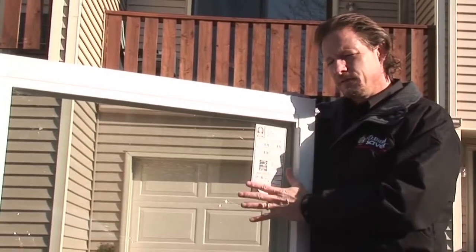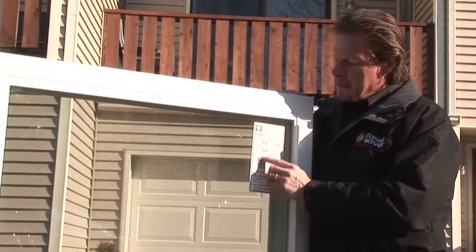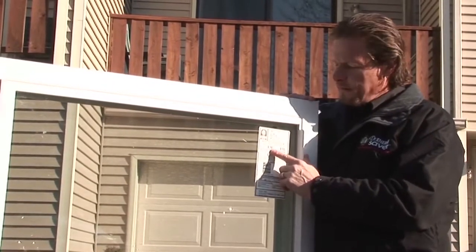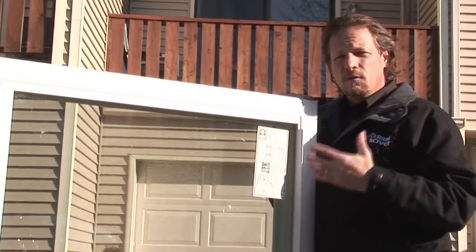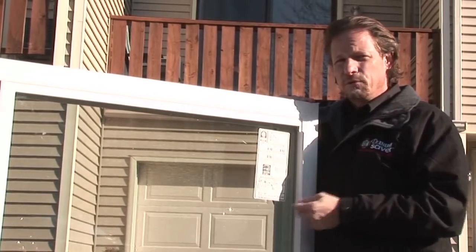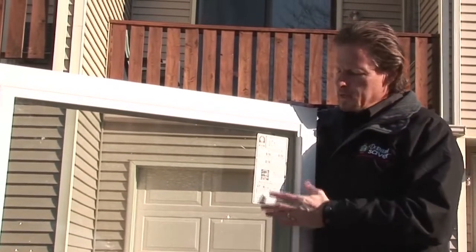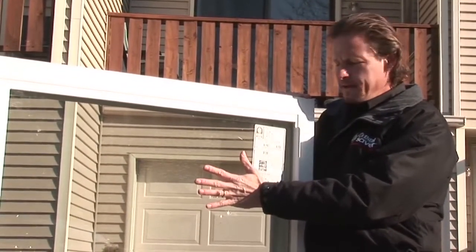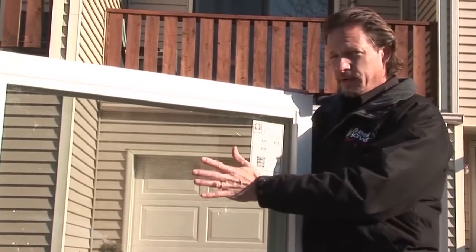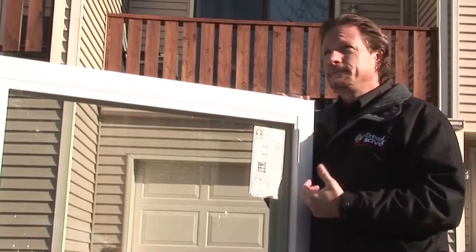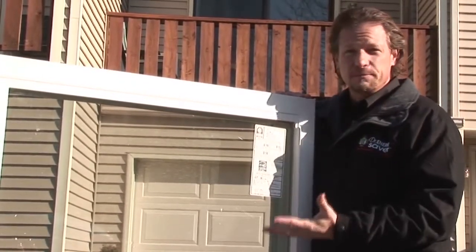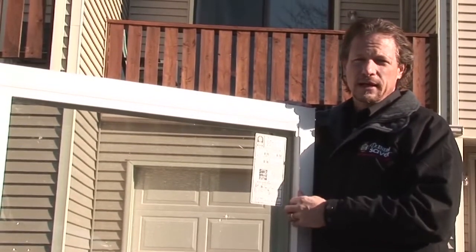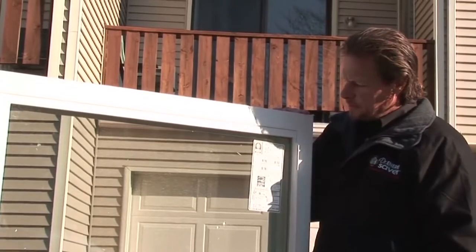That's the R value of this window, 3.33. If we had a U factor of 0.5, for example, then 1 divided by 0.5 is 2. We have an R value of 2. So compared to a window with a U factor of 0.5, this one with a U factor of 0.3, we actually have 2/3 better energy efficiency overall with this window compared to a window with a U factor of 0.5.